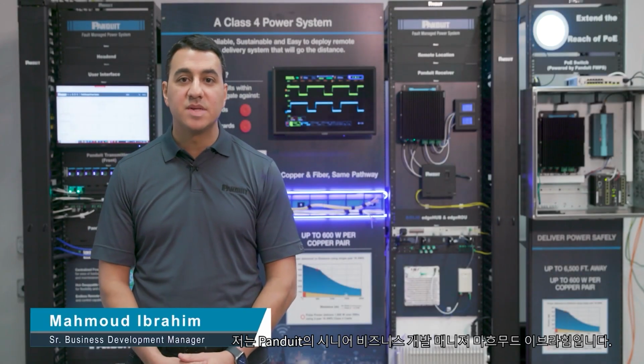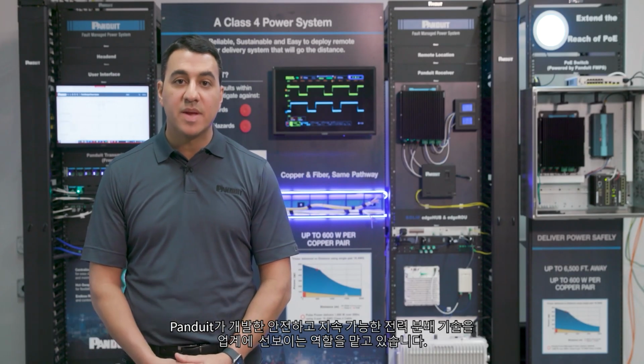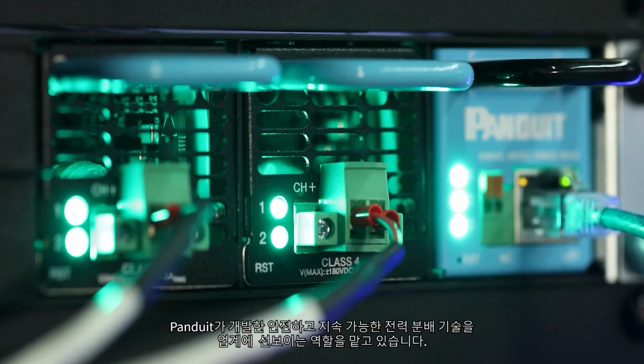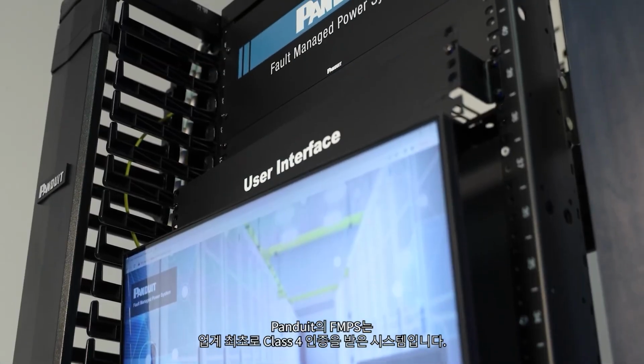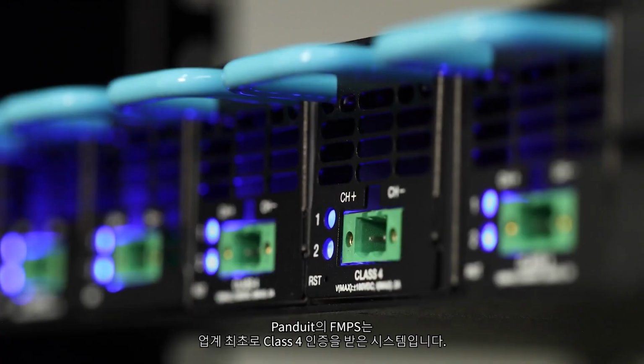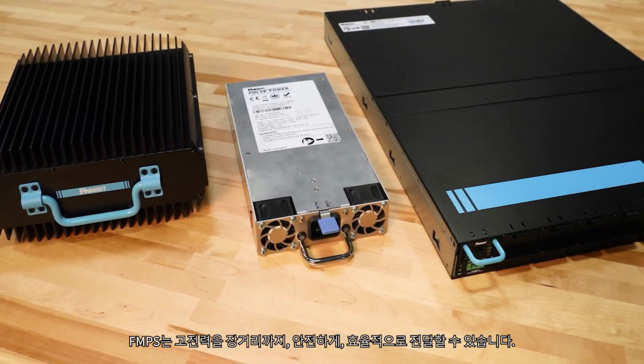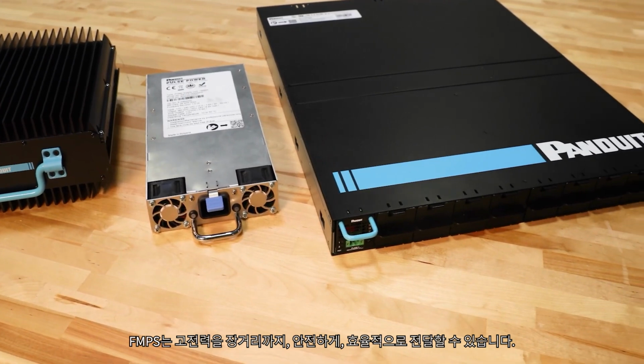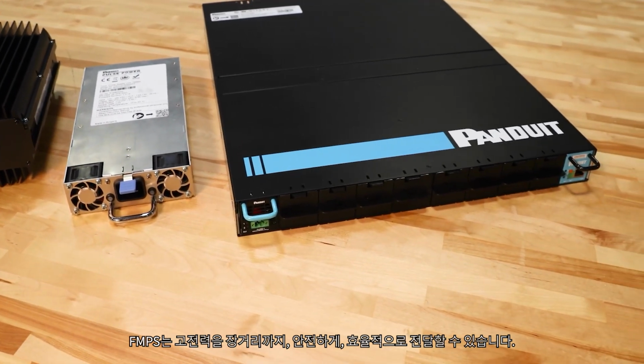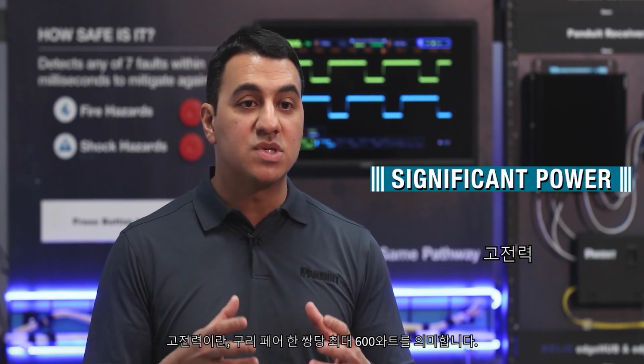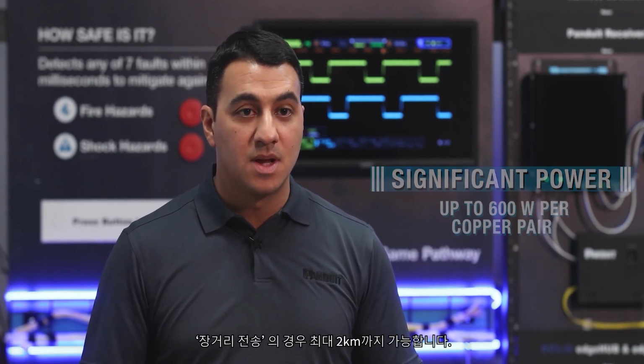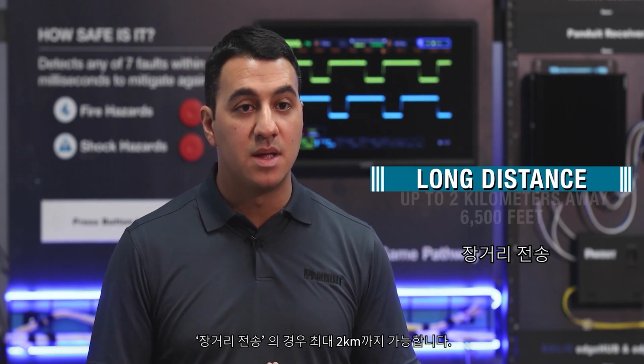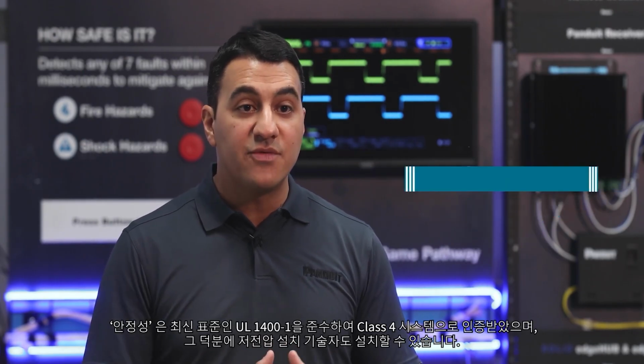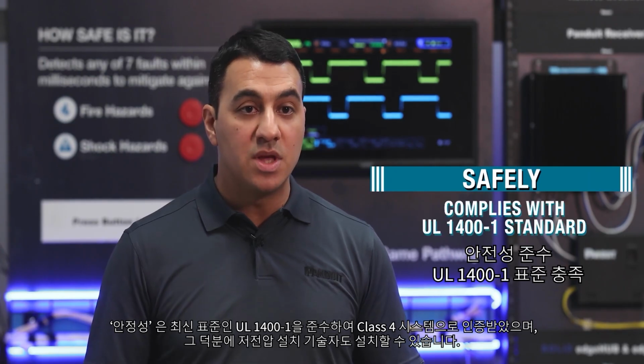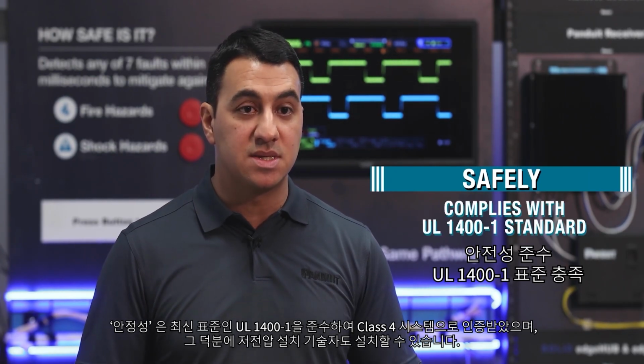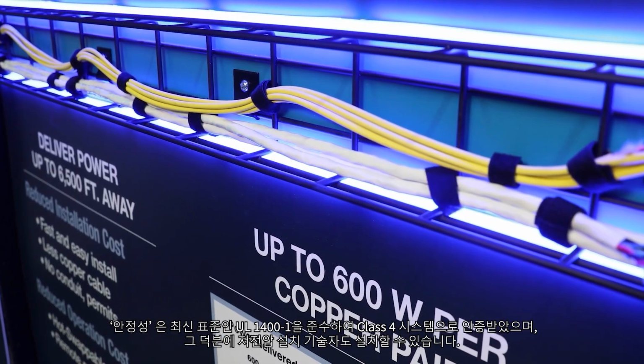I'm Mahmoud Ibrahim, Senior Business Development Manager at Panduit, in charge of bringing Panduit's recent innovation in safe and sustainable power distribution to the market, Panduit's Fault Managed Power System, FMPS, the first Class 4 listed system in the market. Panduit's FMPS allows you to deliver significant power over long distances safely and efficiently. When I say significant power, we're talking up to 600 watts per copper pair. Long distance, we're talking up to 2 kilometers away, about 6,500 feet. Safely, because it complies with the most recent standards, the UL 1400-1, which allows it to be a Class 4 listed system. That allows it to be installed by a low voltage installer.